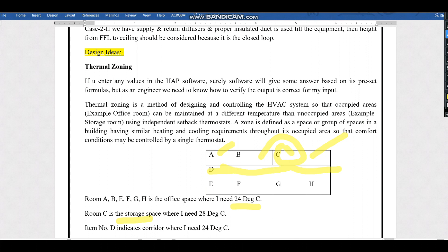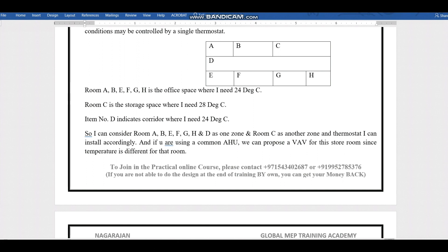Room C is storage, so a higher temperature is acceptable — we can keep it at 28 degrees. Room D, the corridor, should also be maintained at 24 degrees. If we have a package unit or AHU, for the room with a different temperature setpoint like Room C, we provide a VAV. All other similar rooms use a single thermostat for control.